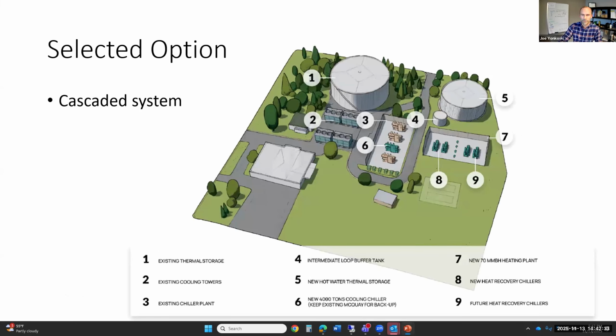This is a schematic of the existing and new plant. The chillers that are turquoise color are new, and the brownish ones are already existing. There's an existing chilled water storage tank, which David talked about earlier, existing cooling towers, and then there will be high side heat pumps, which are part of that Cascade loop, in a new separate building, and hot water pumps also in that building. We're also putting in a hot water storage tank, which is number 5 on the diagram. And there's also a small intermediate tank, which is number 4, to provide enough time for the heating and cooling equipment to adjust when loads are changing.